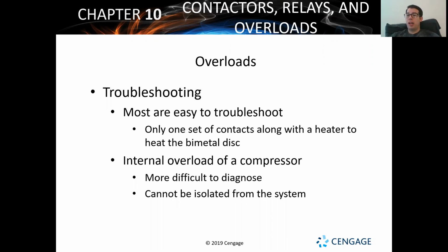But the other thing he told me was, hey, you've got a problem with overheating, so start looking for issues with overheating. Check things like airflow. If you've got a blower motor and it's not getting enough airflow, it's going to overheat. It's going to have an open winding if it's got an internal overload system on it. But for compressors, you're not going to be able to get to those overloads. They're sealed inside that hermetic compressor. So it's not just diagnosing yes, it's a bad compressor, no, it's a good one.